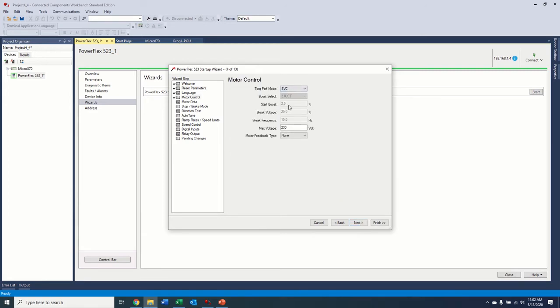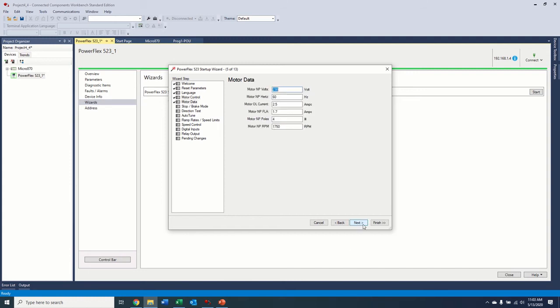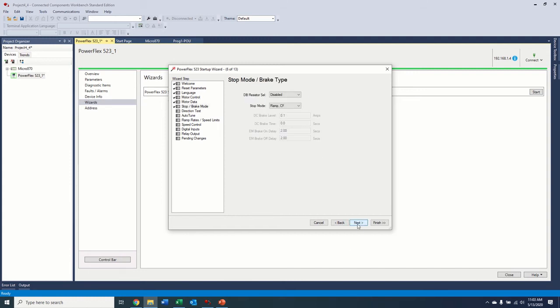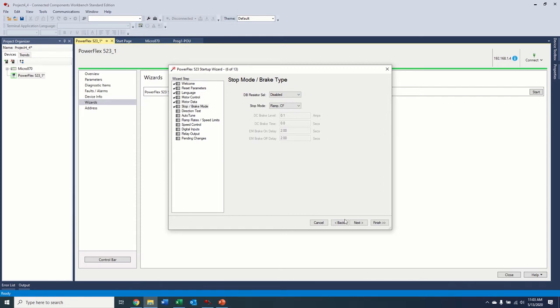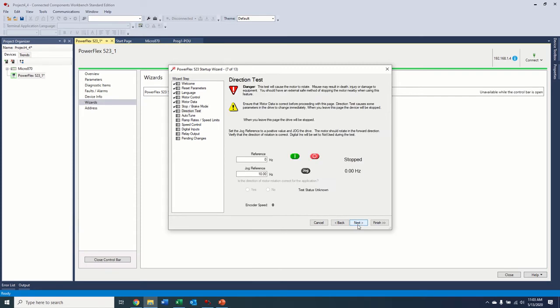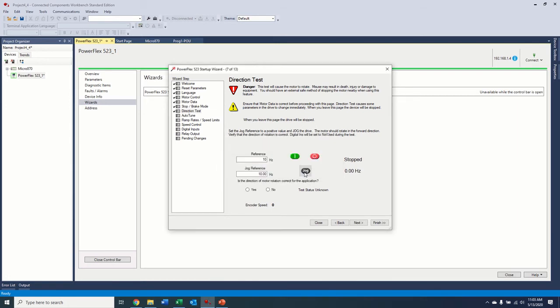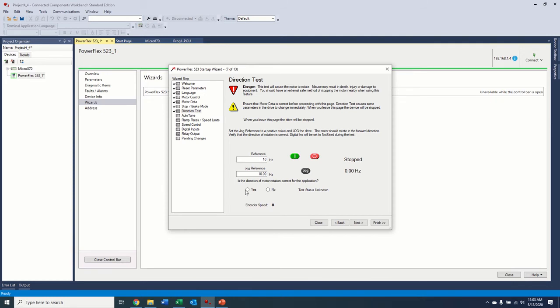So all this as well, this can all be changed as well. But like I said, I have a demo box here. So I don't want to mess too much with the power side of things. Nameplate data, I'm going to leave alone. If we had a brake resistor, which I do not, you could enter your brake resistor information here. So a direction test. So here, if you're hooked up to the drive, you can give it a reference to watch the motor spin. And just to let it know, okay, did we go the right direction or not? And if not, it'll reverse its polarity so that it does go the right direction. But we're good.